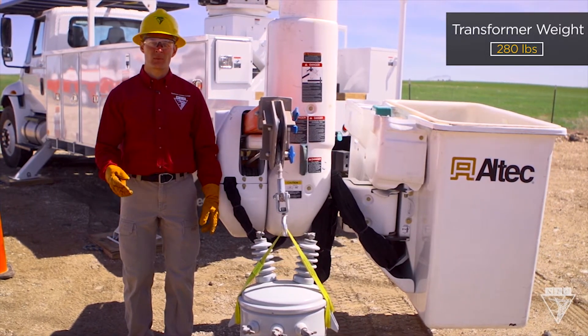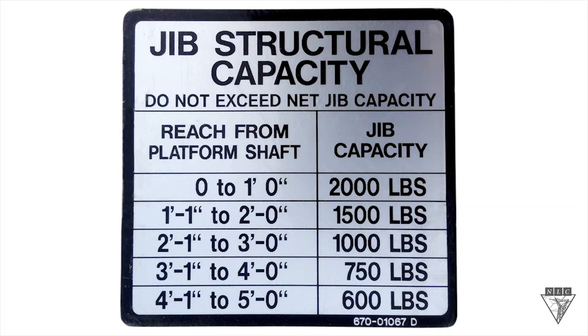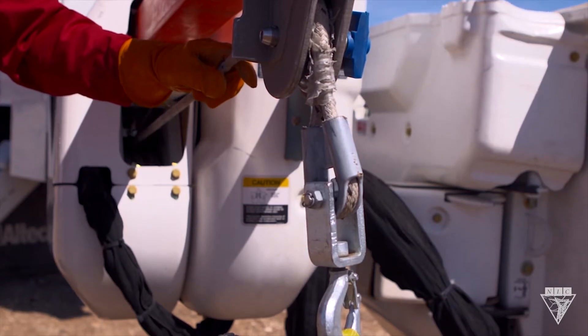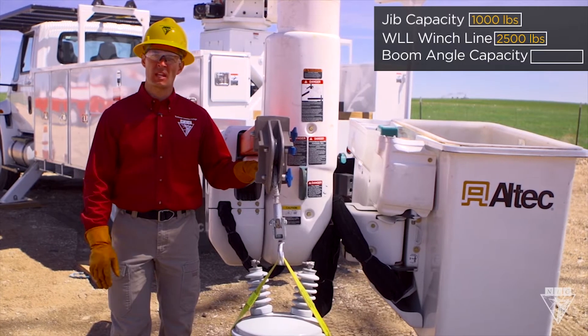This Altec truck has a jib capacity placard on the top side of the jib. Here I can find the max weight that can be lifted at different extensions. To install this transformer, I know I'll need to extend it about two and a half feet, which puts me at a limit of 1,000 pounds. This winch line has a working load limit of 2,500 pounds, so I know I'm safe here.